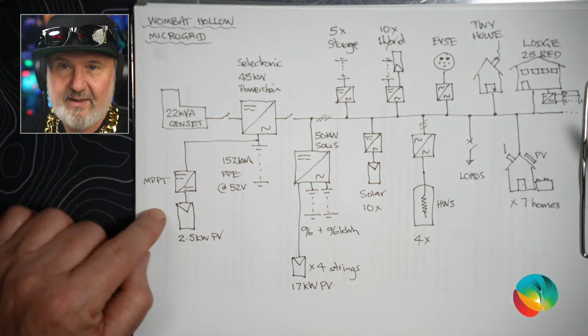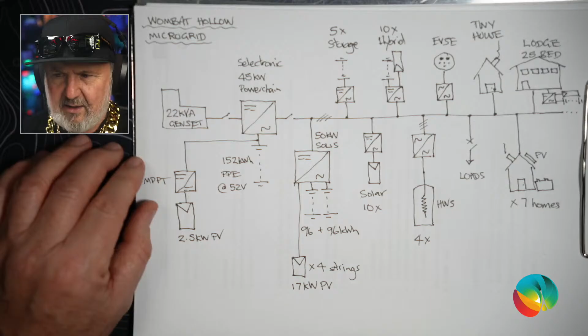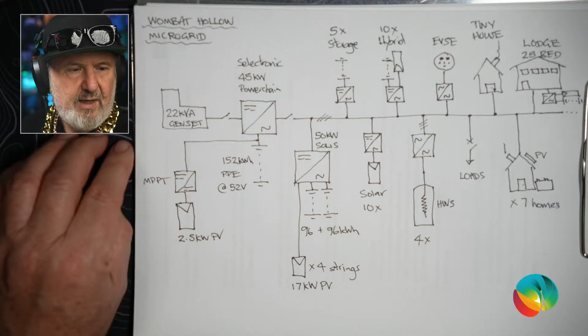We also have, as I've been talking about, a small black start protection system, which is just a little 2.5 kilowatts, which is still quite a lot, but little MPPT-driven DC coupled to keep these batteries alive. And these batteries are, I think I've got 40 Life 4838Ps from Power Plus Energy. So that gives me around 152 kilowatt hours of usable energy in that battery bank. So that's the grid forming system. We just call it the microgrid system here at the lab.